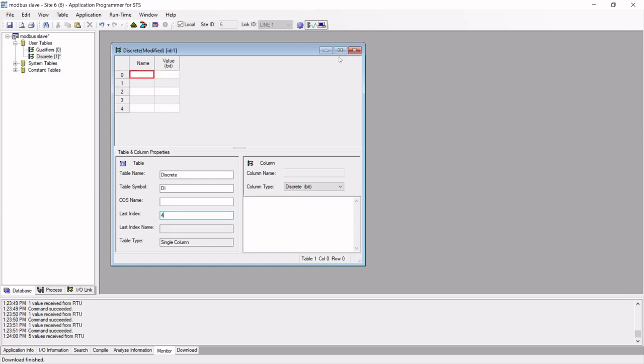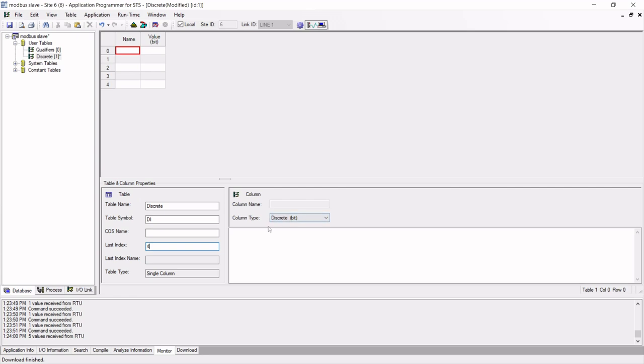Now, to be able to map this data back into a MODBUS master, we need to work out what the addresses are. And here is a formula that MOSCAD provides us with. ACE3600 data is mapped into the MODBUS database by using the following default formula, where Z is the table number. Down here on the right hand side, you'll see we have that information.